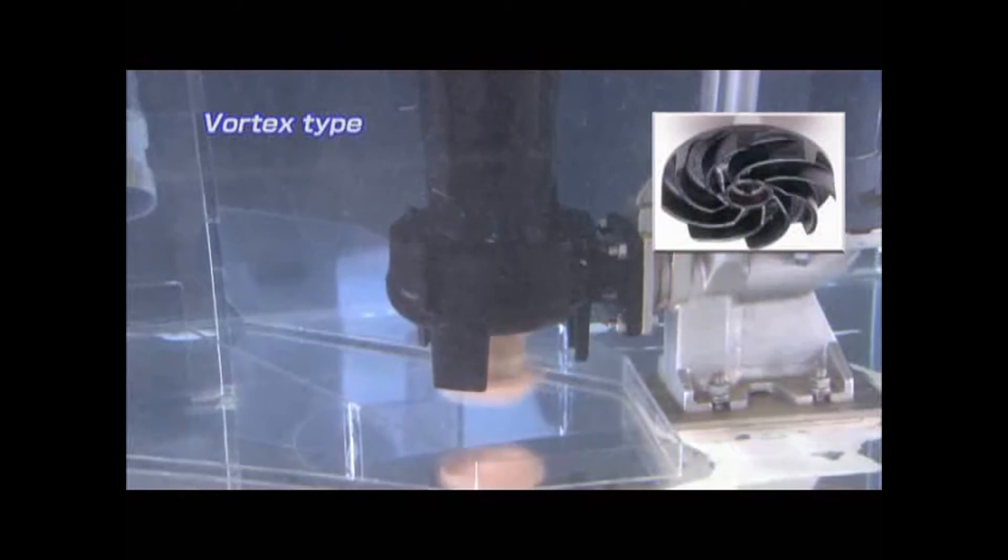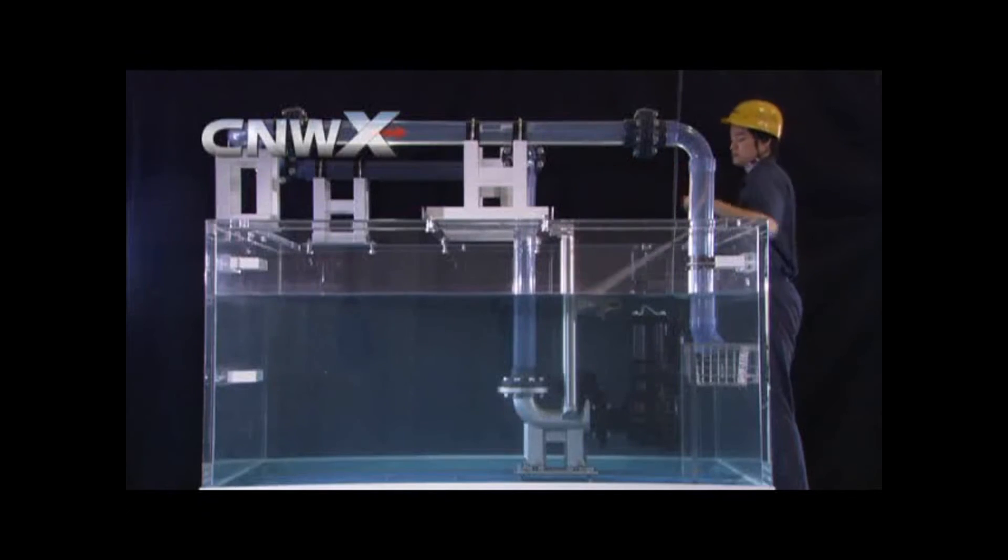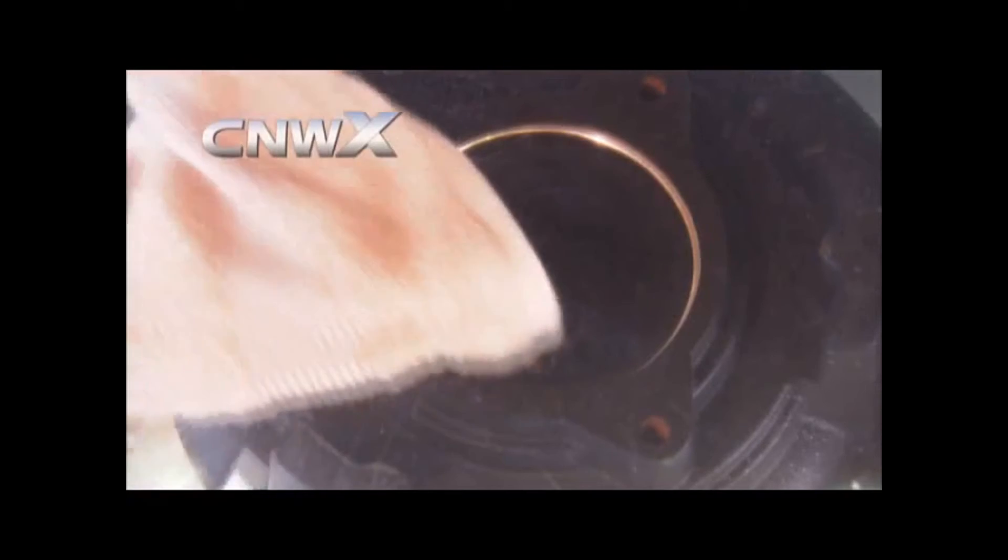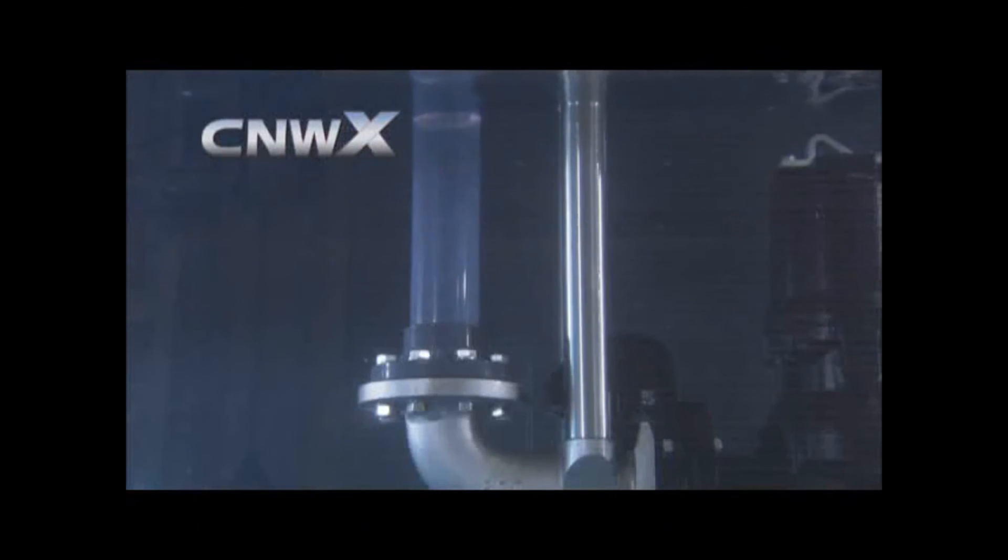Clogging occurs with the conventional vortex type pump. What do you think will happen in the case of the non-clogged scroll submersible pump? As you can see here, even an item such as a towel which is liable to become entangled passes through the pump without clogging it.